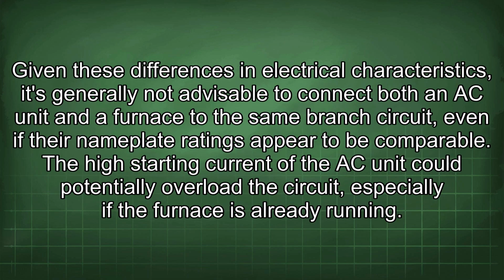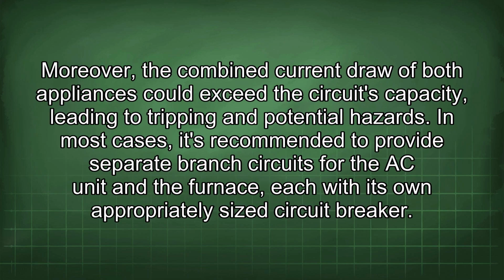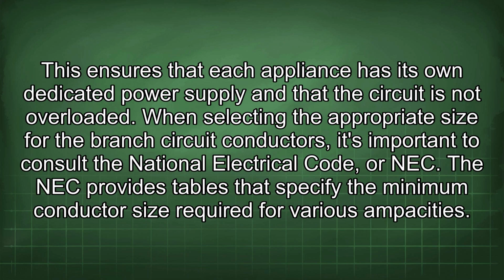Given these differences in electrical characteristics, it's generally not advisable to connect both an AC unit and a furnace to the same branch circuit, even if their nameplate ratings appear to be comparable. The high starting current of the AC unit could potentially overload the circuit, especially if the furnace is already running. Moreover, the combined current draw of both appliances could exceed the circuit's capacity, leading to tripping and potential hazards. In most cases, it's recommended to provide separate branch circuits for the AC unit and the furnace, each with its own appropriately sized circuit breaker. This ensures that each appliance has its own dedicated power supply and that the circuit is not overloaded.